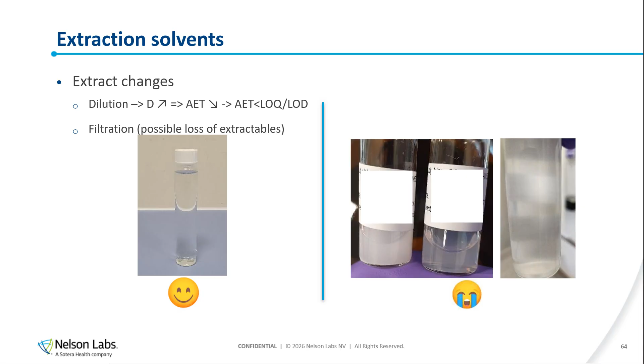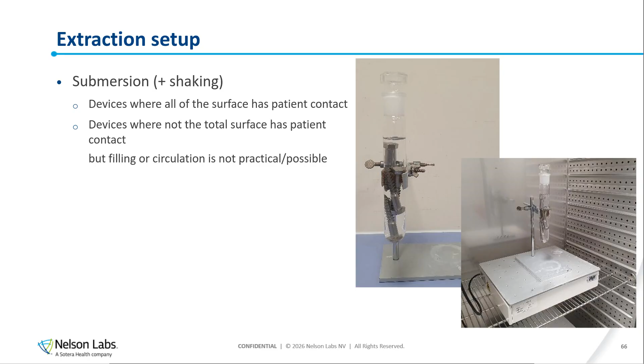And we have 3 types of setups. The first one is the most used, which is the submersion and shaking incubation. These are just devices where all of the surface has patient contact, but also some devices where not all of the surface has patient contact, but the 2 other extraction methods are not possible. The next one is a filling, and then also a shaking incubation. That is where the outside of the device never has patient contact, and then a submersion would be too extreme. So you want to do a filling and shaking incubation.